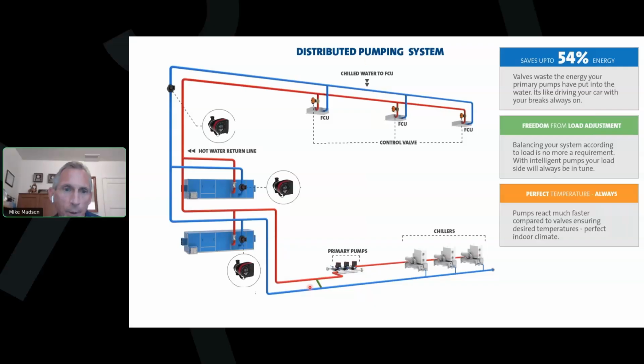Now with distributed pumping, we don't have a big secondary pump skid right here. Instead, we've distributed those pumps to the loads. So you can see I've got a smart pump on the air handler unit here. I've got a smart pump on this air handler unit. Here I have 1 pump managing 3 fan coil units. And like we mentioned earlier, if we're doing a group of fan coil units, the control mode would be proportional pressure on that pump. And on these pumps here on the air handlers, we're going to be controlling to leaving air temperature.